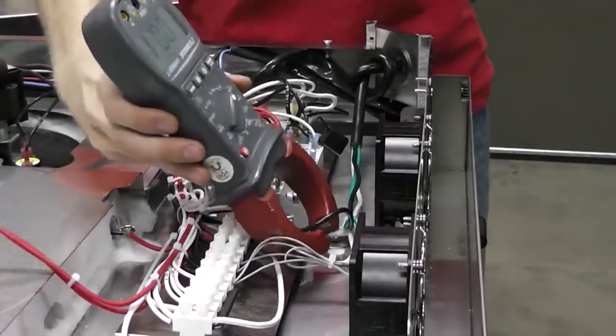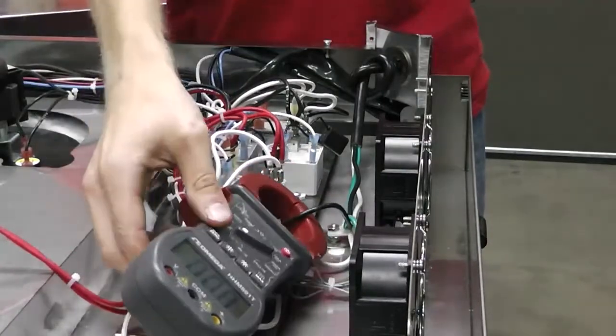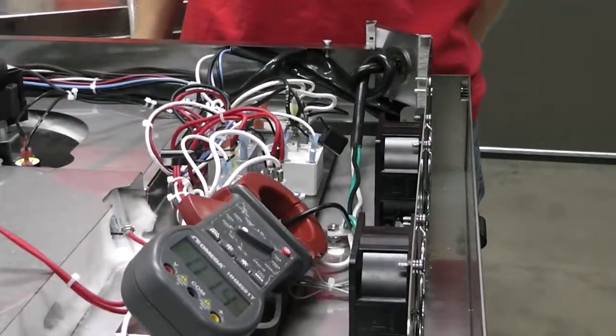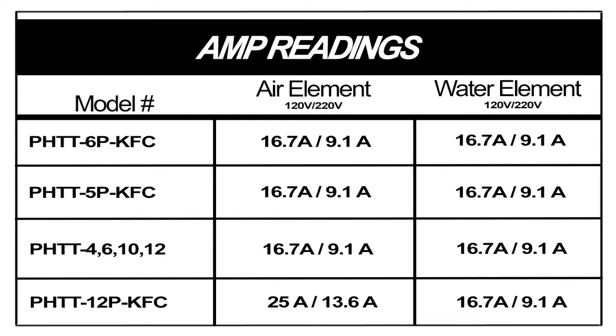Clamp your amp probe on the black cord wire that's your incoming power line. When measuring incoming line power, for 120 volts, add 2 amps for the fans, or at 220 volts, add 1 amp. Current readings may vary slightly than those listed above. This is normal and dependent on the actual voltage and element resistance tolerance.